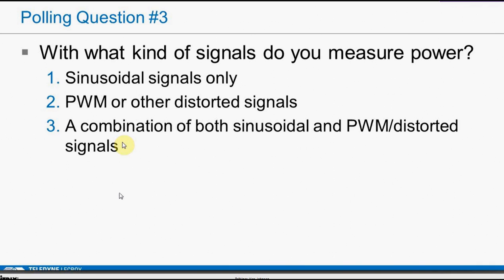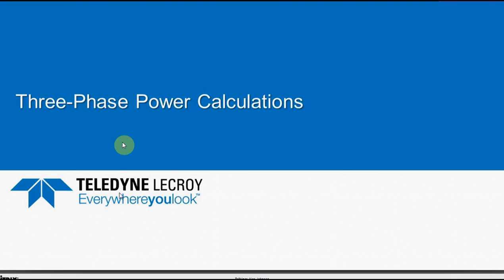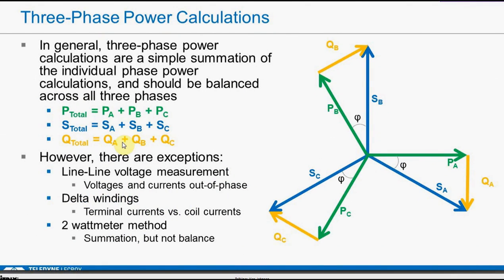Okay, so now let's go to a three-phase case. So what do we do for three-phase? Well, remember, we've got three voltage and three current vectors, so we're going to have three power quantities as well, one power quantity for each phase. And if I look at these, as I described before, there is a real component in green, a quadrature or reactive power component in orange, and the apparent power in blue. And so, very simply, if I can calculate the voltage and current, and I can calculate the power for each phase independently, then I can just sum the three phases up and calculate the total value of the three-phase system.